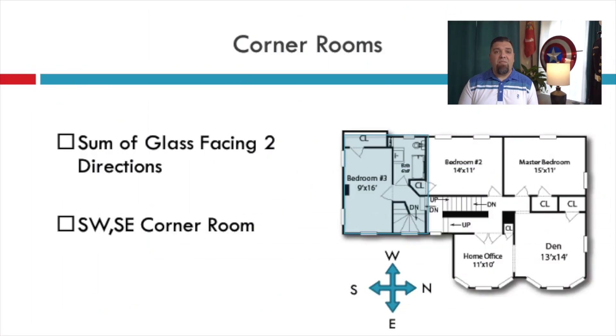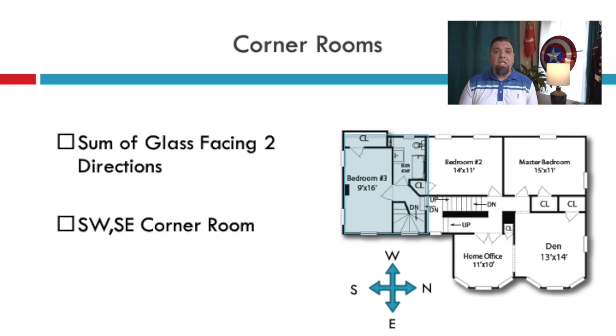You want to stay away from combining skylights with southeast or south-facing glass unless it's in the same room — same for southwest and south glass. Just above that in my house is my daughter's room and bathroom, which has the same issue with south and east-facing glass — this is a corner room. Remember: the sum of all south-facing glass plus the sum of all east-facing glass does not equal what it would be if it faced southeast. There are no shortcuts — you have to enter it correctly into the load calc to get a combined sensible gain for the room.